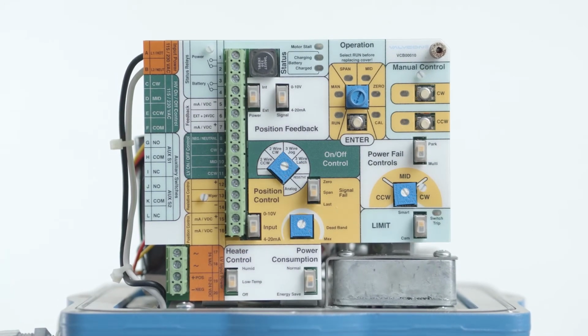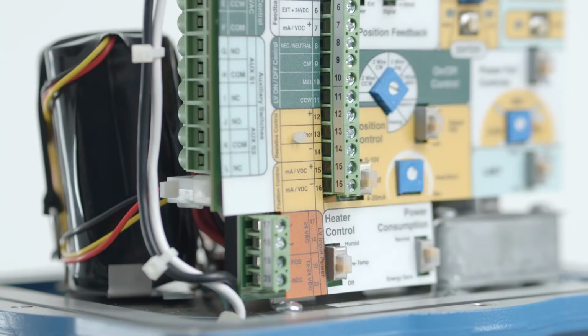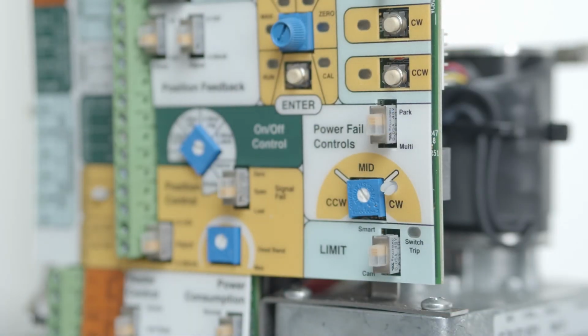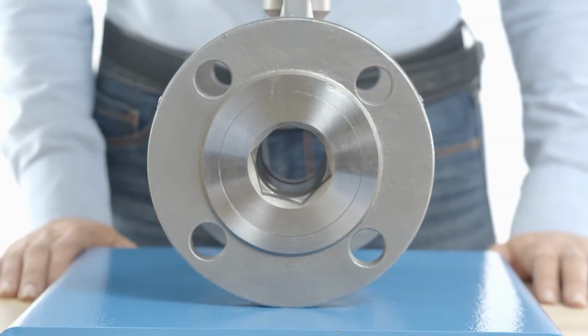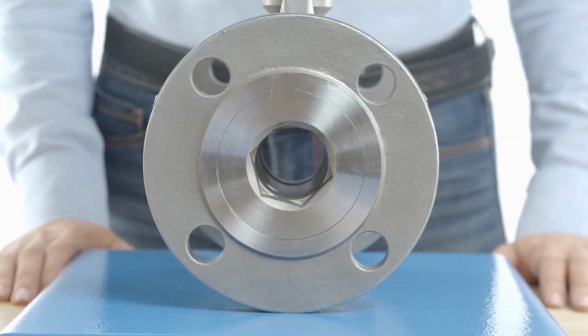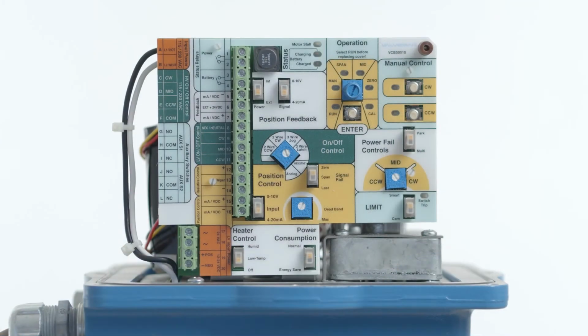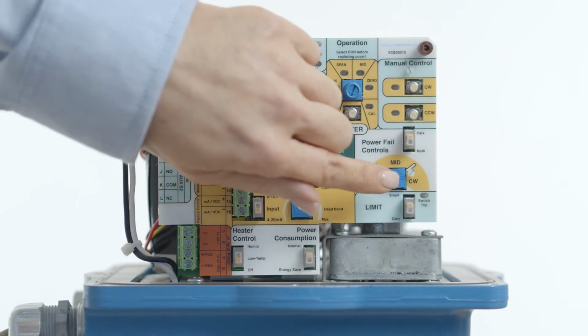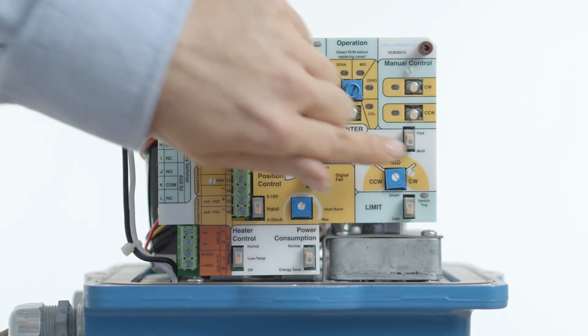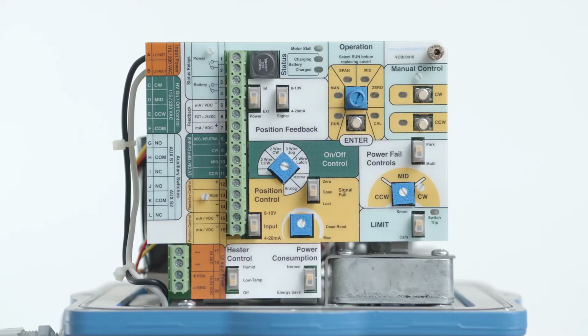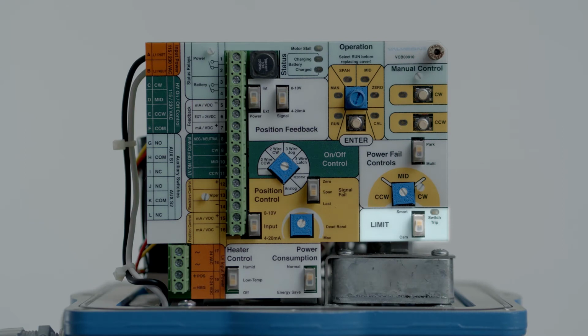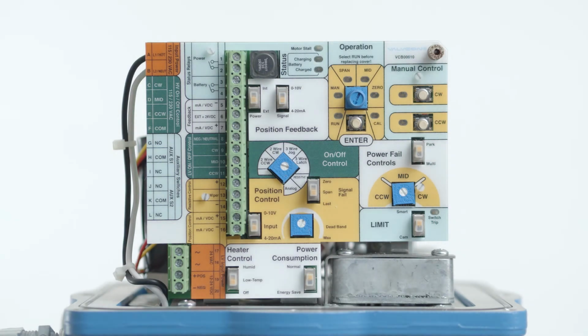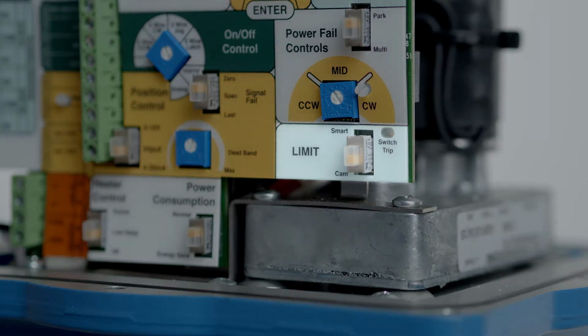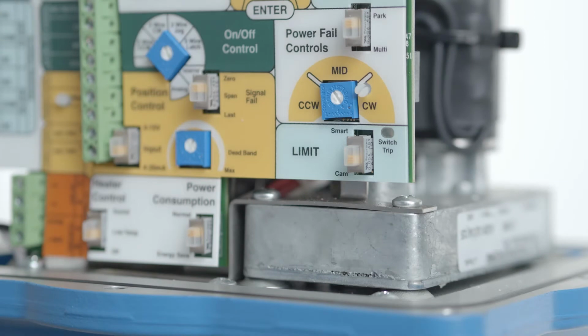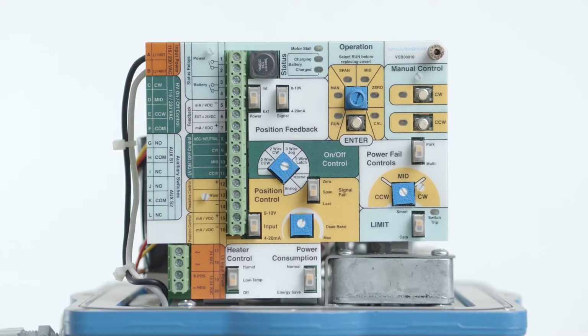The actuator is factory configured for 2-wire CCW operation. To change the settings and/or fine-tune the actuator to the valve, damper, or other final drive element, perform the following. First, select desired limit type, Smart or CAM, by sliding the switch down to select CAM or up to select Smart. Selecting Smart will enable other features on the board such as position feedback and 3-position operation. Selecting CAM will allow the actuator to drive between the end of travel limit switch settings. Smart mode is the default configuration prior to shipment from the factory.